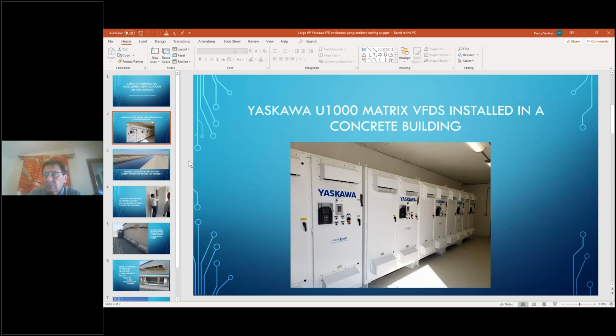NEMA 3R, it turns out, doesn't cost that much more than NEMA 12. NEMA 12 being oil tight, dust tight, NEMA 3R being rainproof, and in the case of Yaskawa's implementation of NEMA 3R, it is also NEMA 12. So it's oil tight, dust tight, and it resists outdoor weather conditions such as rain. It's more equivalent to the ingress protection rating IP54. And I'm not going to go over ingress protection ratings now, just Google them and you'll see that those two numbers, the first one is particulate ingress, the second one is water. Did I say that right, Craig? Or is it water first, particulate ingress second? But it's one of those two, so Google it.